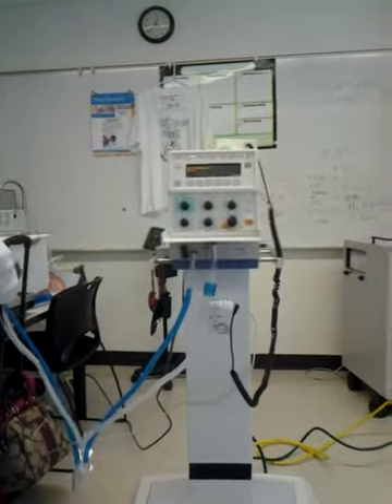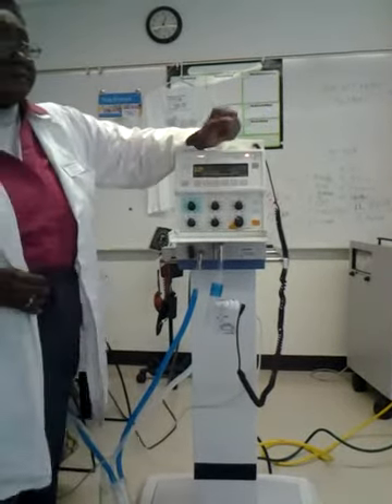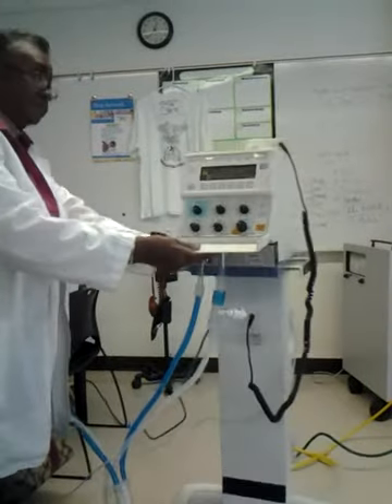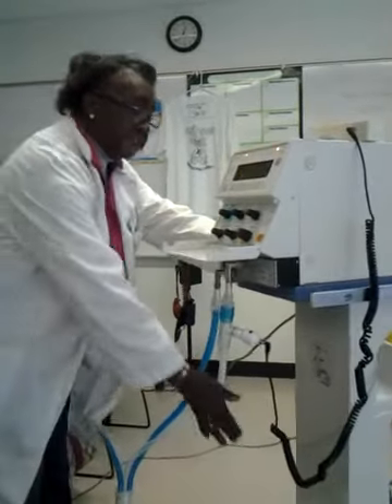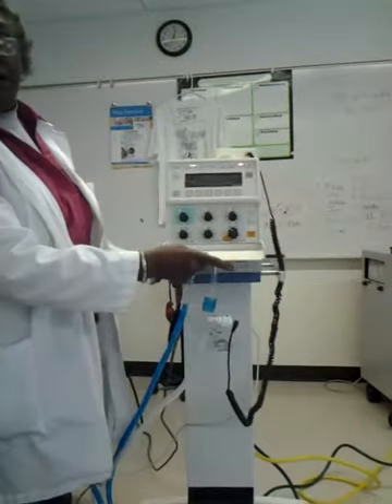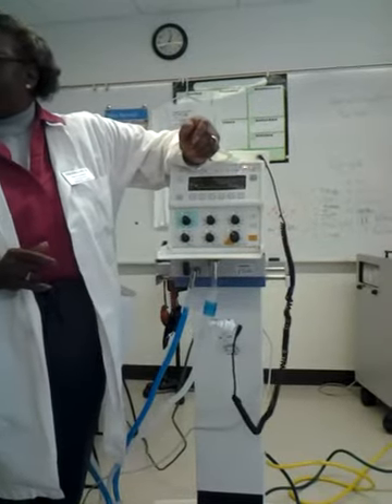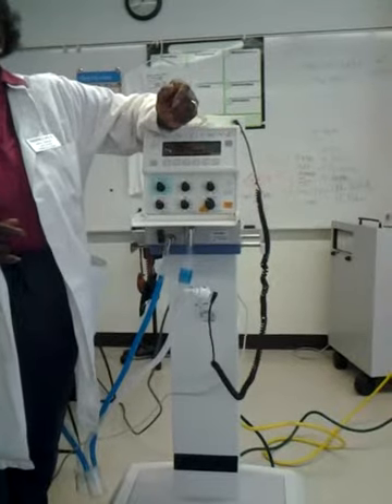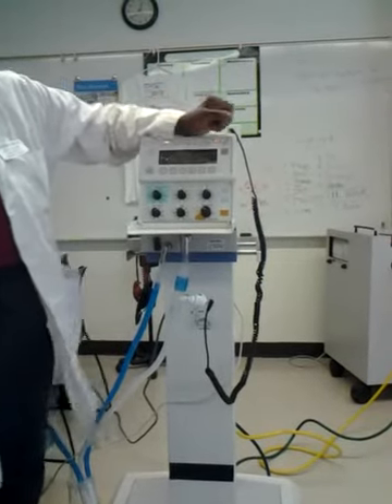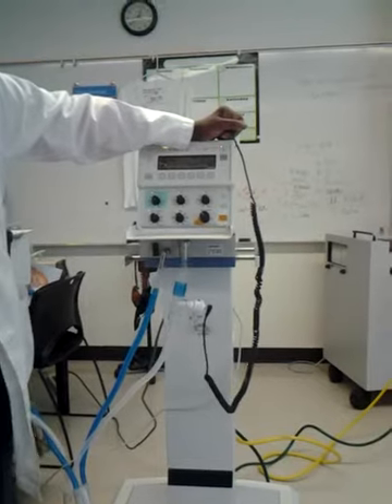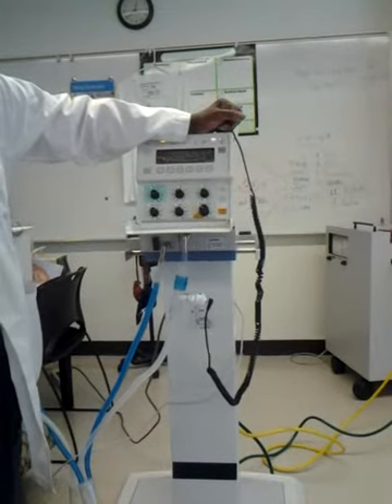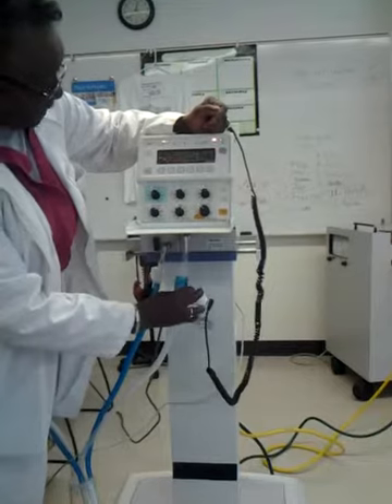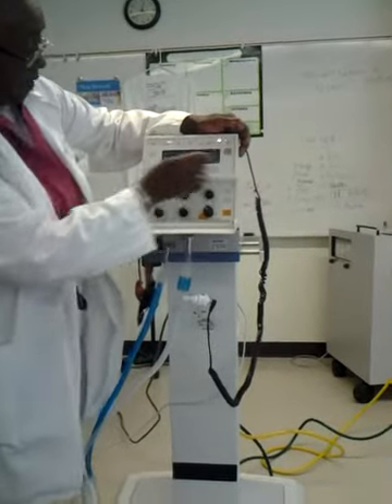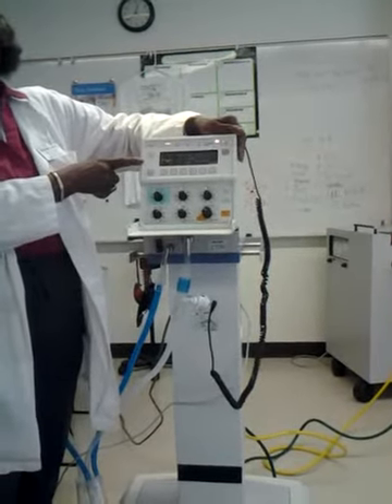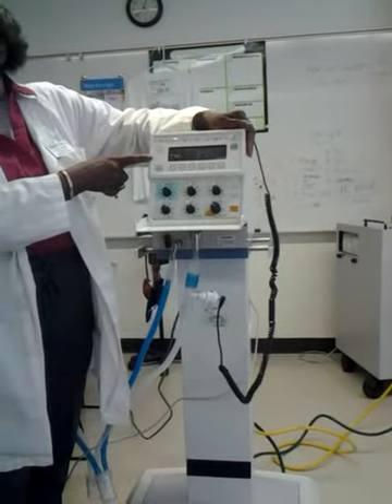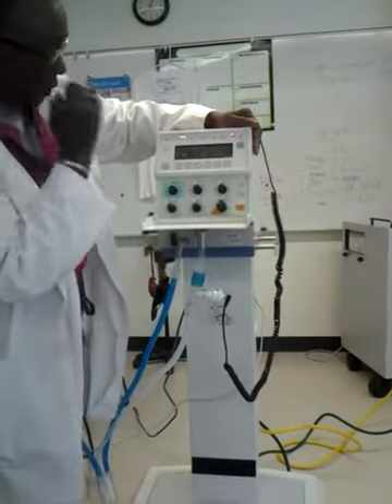Where is that hooked up to the back? So where's the flow sensor hooked up to the back? Okay, this is it. You will always, when you're working with infants, have an oxygen analyzer in line regardless, no matter what. It stays in line the whole time, as you're measuring what's coming out of the machine. And you notice now that I have my flow sensor in, I have a flow waveform. Without the flow sensor, I didn't have a flow waveform.